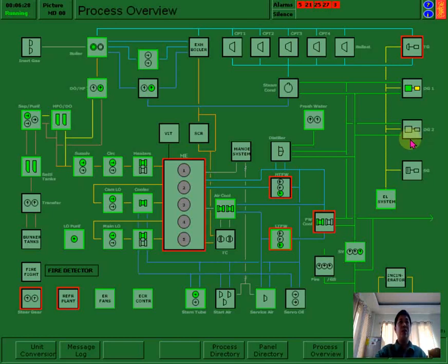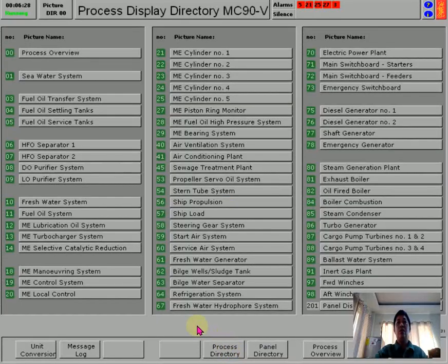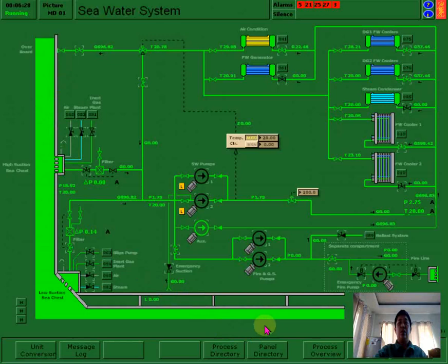Before we start DG2, we will transfer the seawater system and the freshwater system into main pump, because when the DG2 is synchronizing, the auxiliary one is probably automatically switched off.